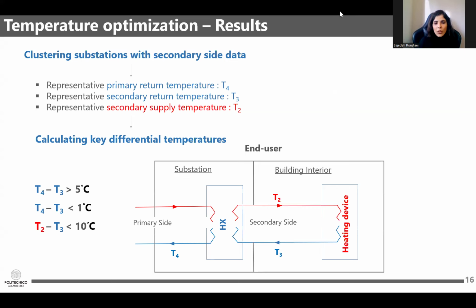For example, we calculated the difference of temperature on both sides of the heat exchanger, T4 and T3. We usually expect this difference to be close, something around 1 or 2, so we set a threshold of 5 to be on the safe side. If the differential temperature was higher than this threshold, it's a sign that the problem is in the substation — for example, the heat exchanger might be blocked and need cleaning. In some cases, this differential temperature might be lower than 1, which is a sign of sensor misplacement, because it's physically impossible otherwise.